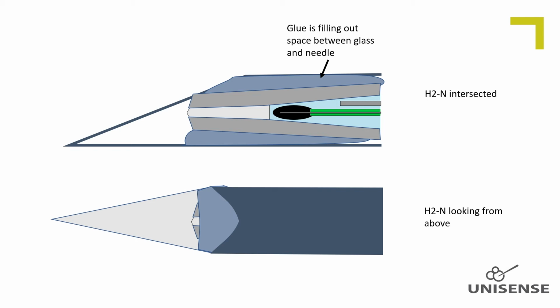This is a schematic drawing of the tip of hydrogen needle sensors and hydrogen piercing needle sensors. The needle protects to some extent the glass, but the sensor tip is still fully exposed to the sample solution. The needle and the glass part of the sensor are glued together inside the needle, so no sample liquid will intrude into the needle. This would otherwise cause a huge carryover effect.